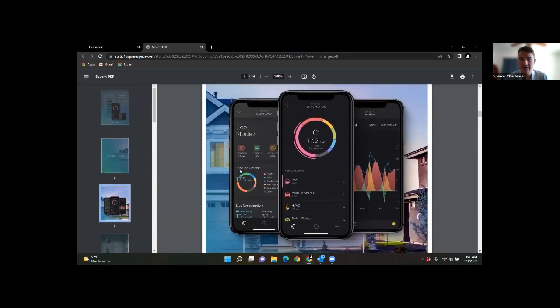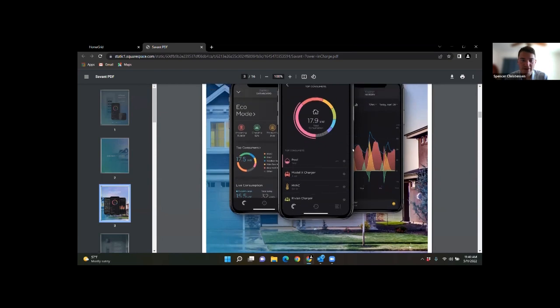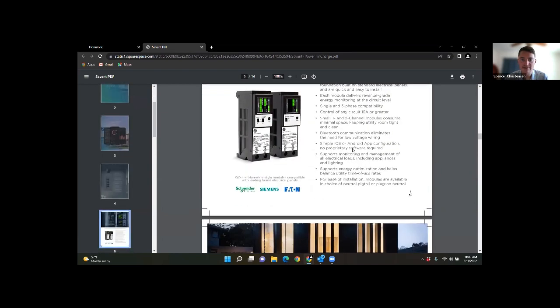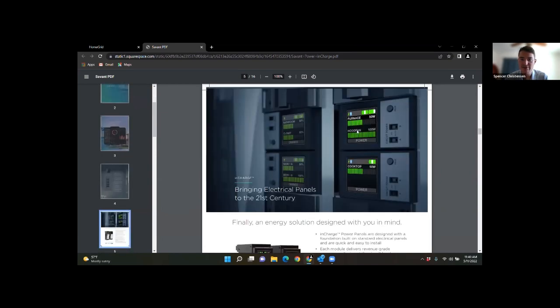It's very affordable, about half the cost of other smart load systems I've seen. Instead of being a full panel, it's a modular approach — these companion modules you put in and tie to the breakers. You don't need to do every load, really just the non-essential automatic loads, like your HVAC or pool pump, loads that kick on automatically and could drain the battery, and you don't want to overload the system.